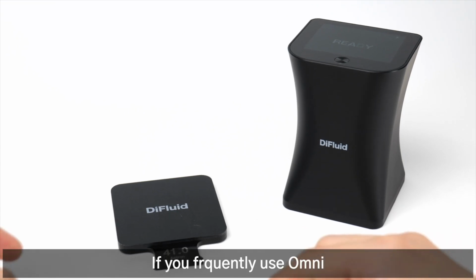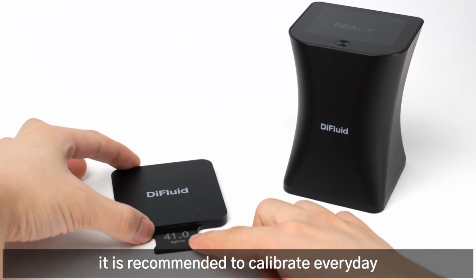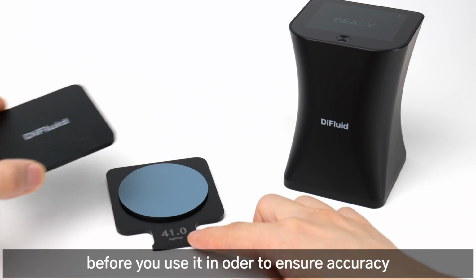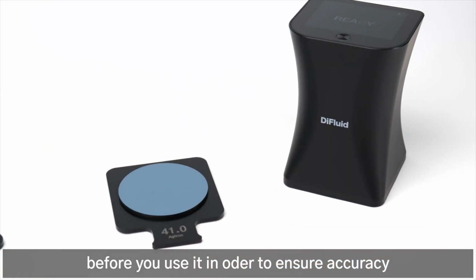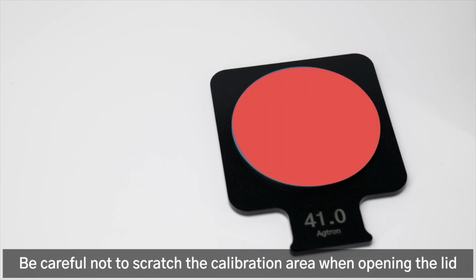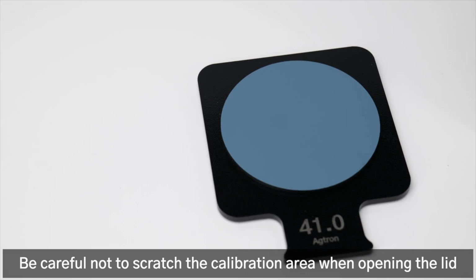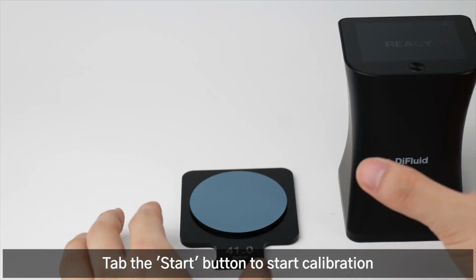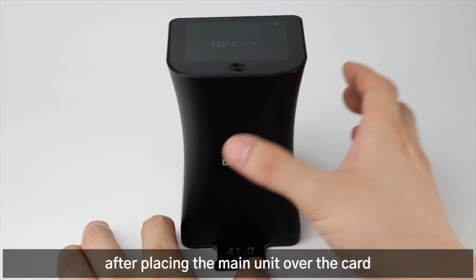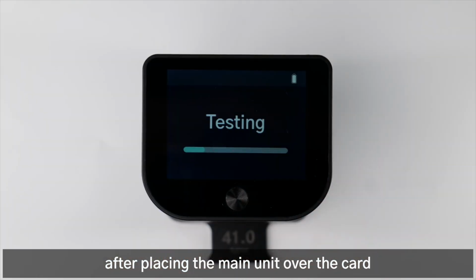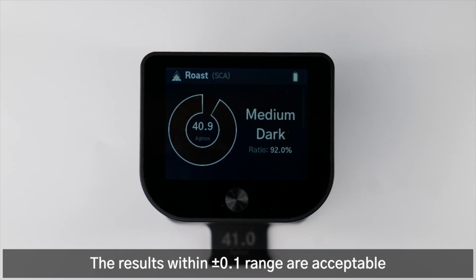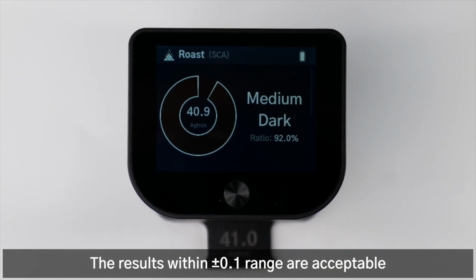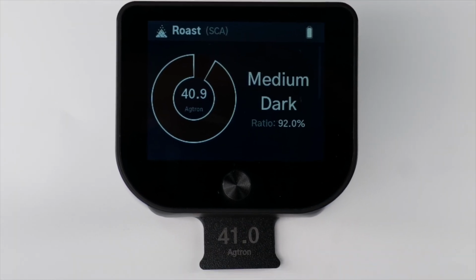If you frequently use Omni, it is recommended to calibrate every day before you use it in order to ensure accuracy. Be careful not to scratch the calibration area when opening the lid. Tap the Start button to start calibration after placing the main unit over the card. The results within plus or minus 0.1 range are acceptable.